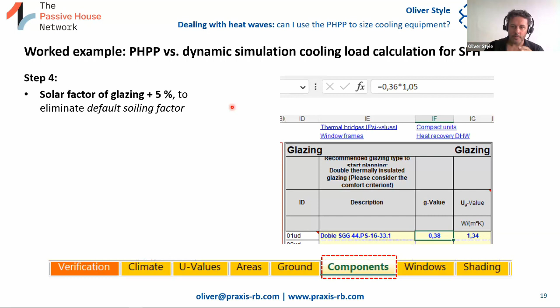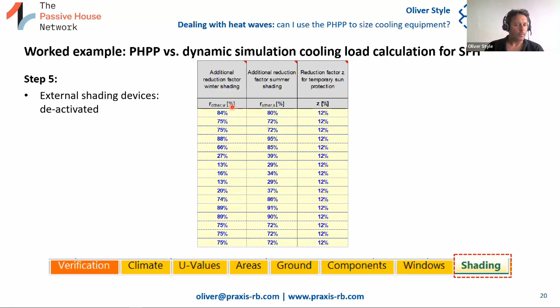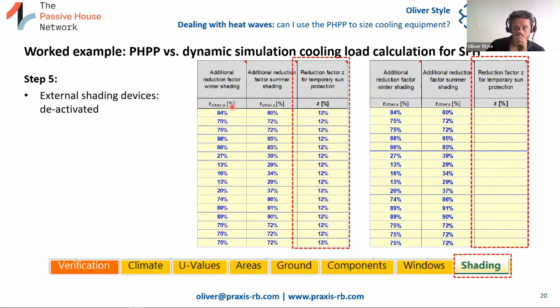Step 5, external shading devices. This is always an issue of debate, but you need to talk to the client and evaluate. In our experience, it can be risky to assume people will use the blinds optimally all the time, unless you have a client who says they've got a control system that's properly controlled. Generally, and in this example, we assume the blinds are not down, so we eliminate that temporary reduction factor for sun protection in the shading tab.